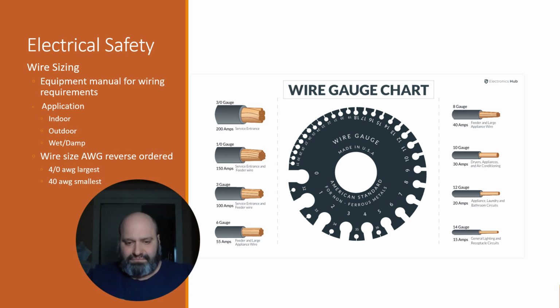It was slightly smaller, but it was not the right equivalent gauge. So I made a big deal about it, and sure enough, the breaker ended up tripping. Why? Because there was high amp draw, because we were trying to push more current than that little wire was able to handle. So we went back to the shop and found the right gauge wire that matched the gauge on that machine. And now, because the breaker tripped, he was thinking it was a bad compressor.